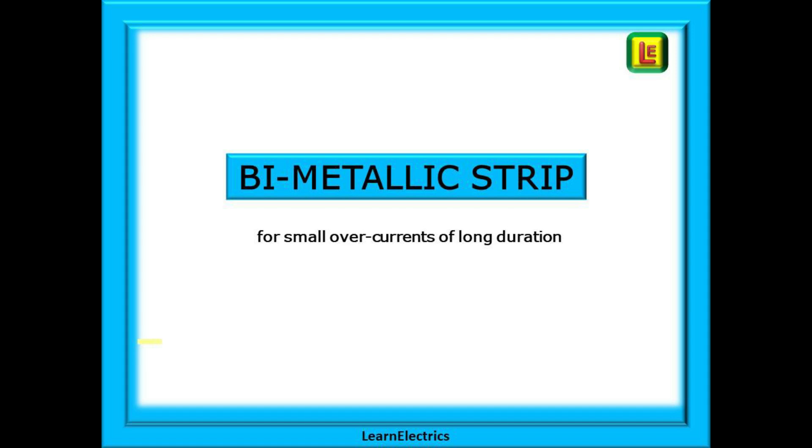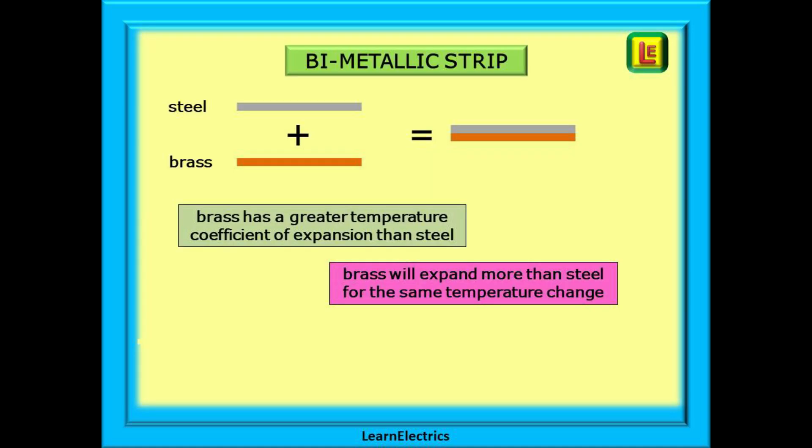Let's start by looking at the bimetallic strip that responds to small overcurrent of long duration. This strip or bar is quite simply two different metals that are physically bonded together. When they are manufactured, the touching surfaces are chemically locked together as one piece of metal.